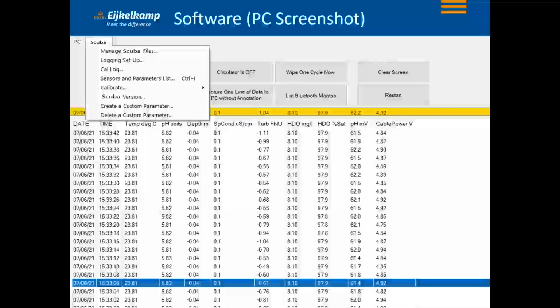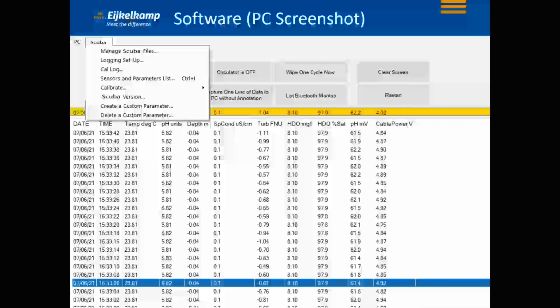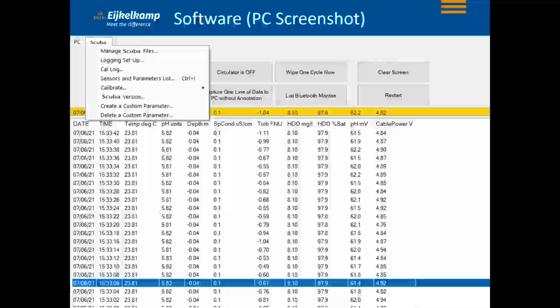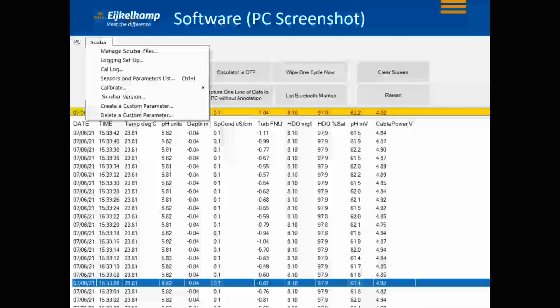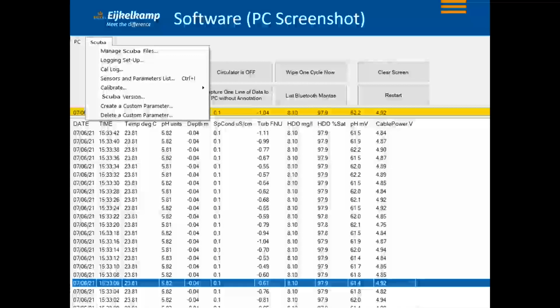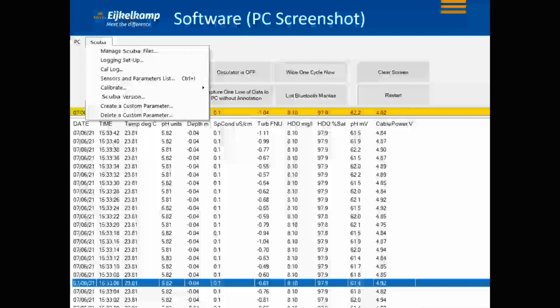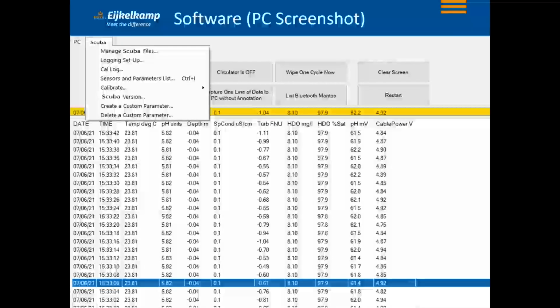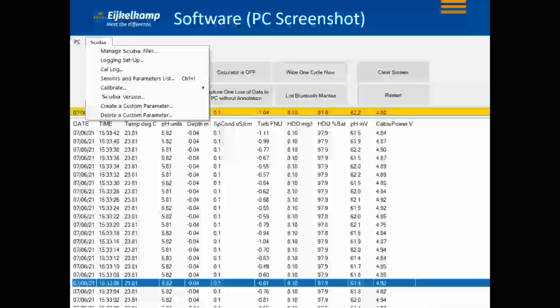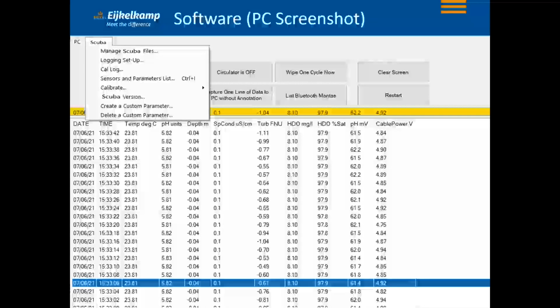There's also the option for a calibration log, where you can register all your calibration results. All the calibration results will be stored, so you can build up a calibration history over time, and if you want to look back for a year, you can look into all the calibration data.